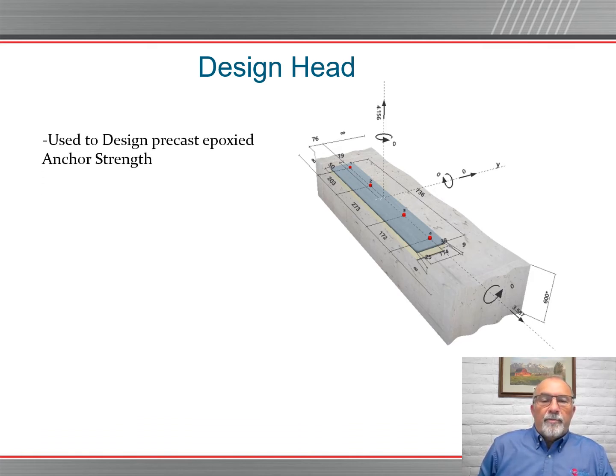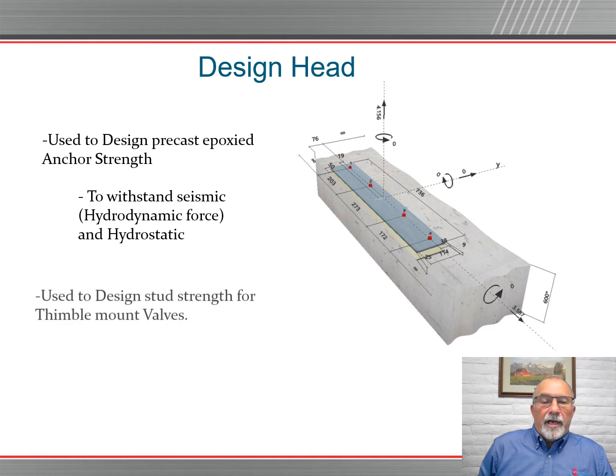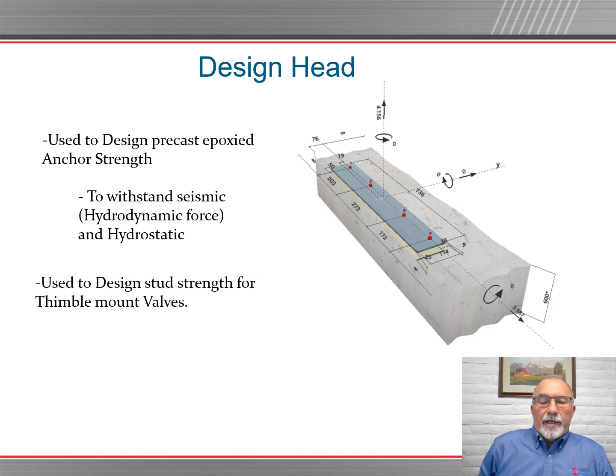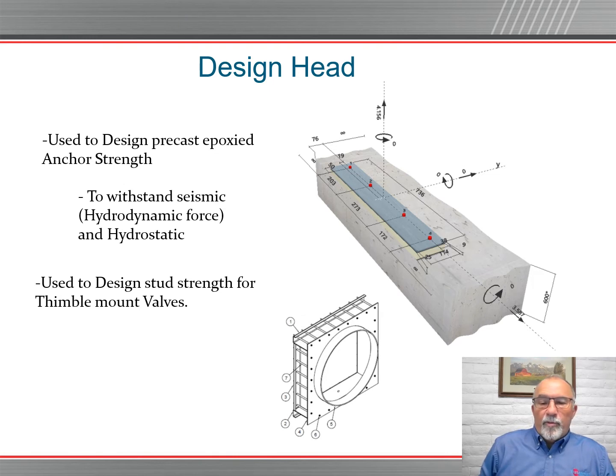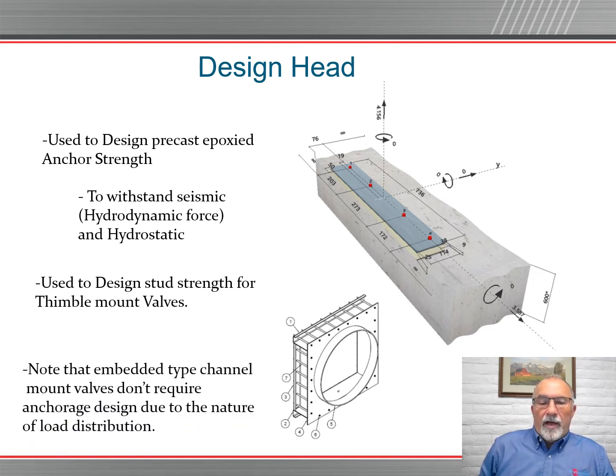and it's used to design precast epoxy anchor strength to withstand seismic hydrodynamic forces and hydrostatic pressures. It's used to design the stud strength for thimble mount valves. We use this similar formula for the embedded valve or the embedded thimbles for mounting if that's the case. Note that embedded type channel mount valves don't require anchorage design due to the nature of the load distribution built into the thimble. Thimbles are cast in place in your concrete wall.